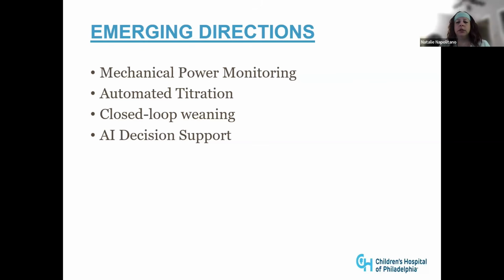So right now, for instance, we have Draeger ventilators and GE monitors at our institution, and it was an over a year-long process to get there. Draeger actually paid for an intermediate company to work through the code between Draeger and GE so that we could get some information from our Draeger ventilators to project onto our GE monitors, and then from there go into the medical record. So we will always have to use an intermediary of some sort, because GE doesn't want to give Draeger their code, and Draeger doesn't want to give GE their code because they're competitors. So that's part of the problem there.